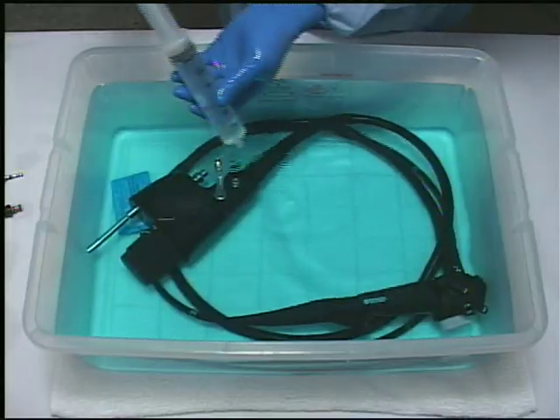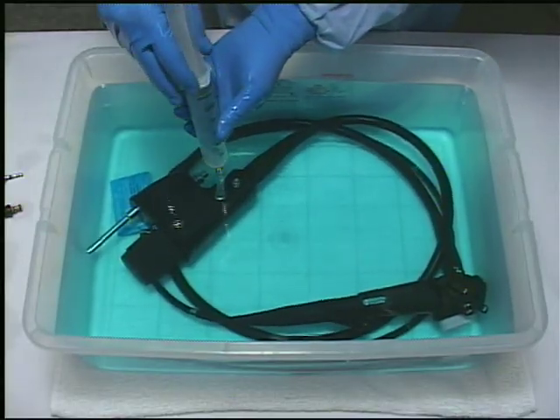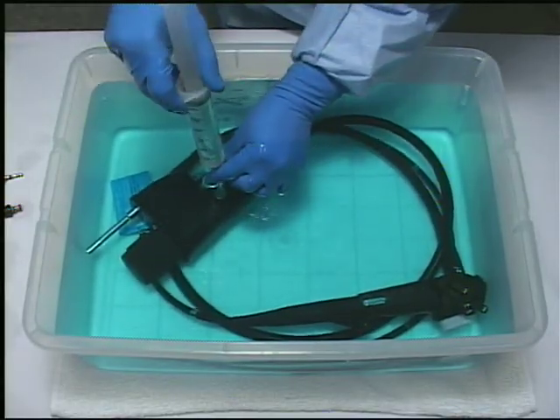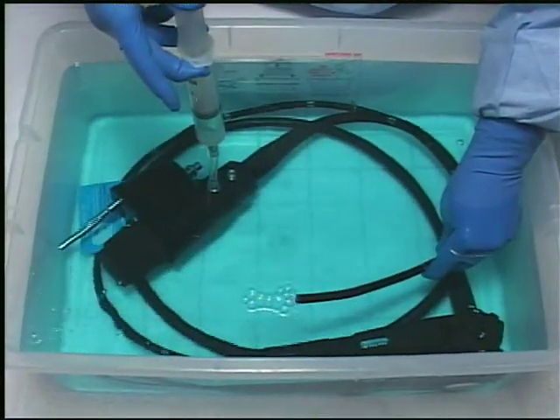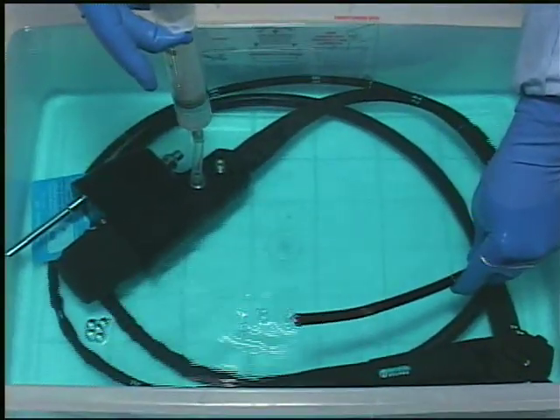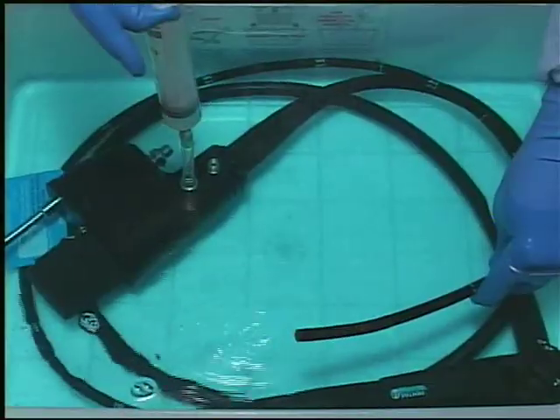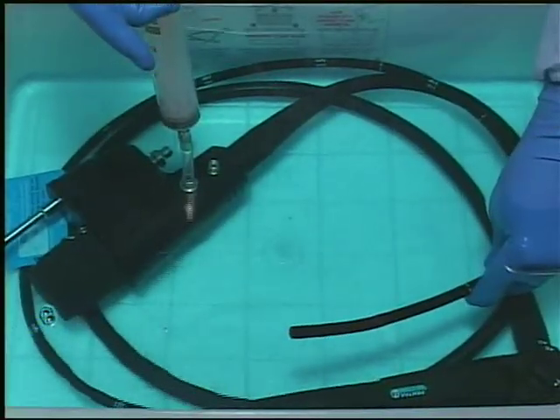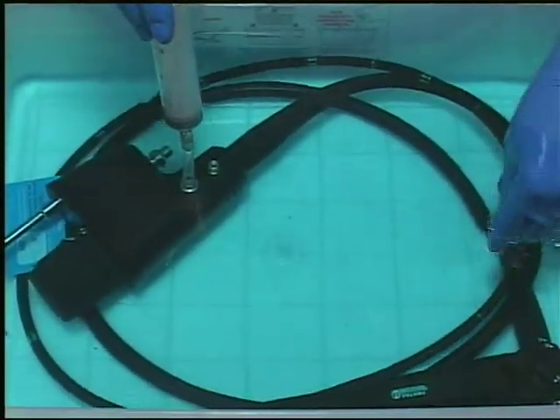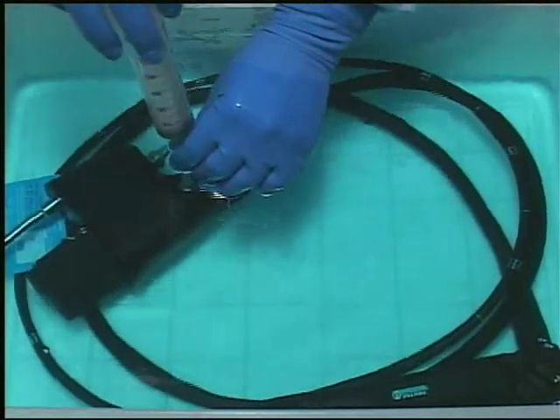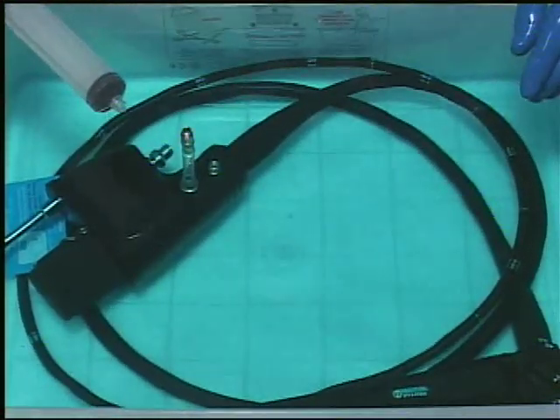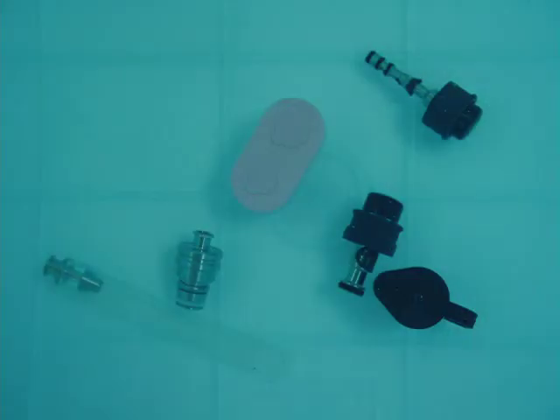Attach a 50 to 60 cc syringe to the suction channel cleaning adapter. Fresh or reused actively effective disinfecting solution should be flushed through the entire suction system. Repeat to confirm contact of disinfectant with all channel surfaces. As long as the entire instrument remains completely immersed and all channels remain filled with disinfectant, all cleaning adapters, rubber inlet seal, and syringes used in previous steps should be removed.